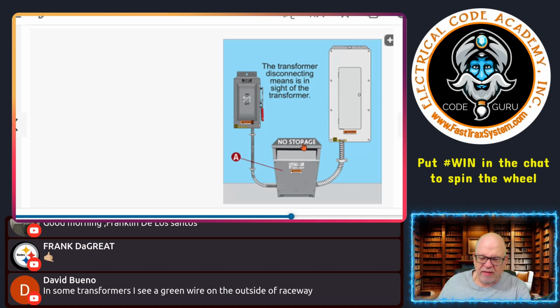So, David says sometimes he sees a green wire on it. So for bonding jumper applications, there are some allowances as long as it's not more than 6 feet, to maintain integrity, okay? That type of scenario. But remember, in most of the transformer applications in this panel, if the system bonding jumper is installed in here, okay, then what we're running through here is going to be 4 conductors, let's say, or it may even be more than that if you've got A, B, and C, and then you have a neutral, and then you have the supply side bonding jumper, which may also run here, okay, in this scenario.